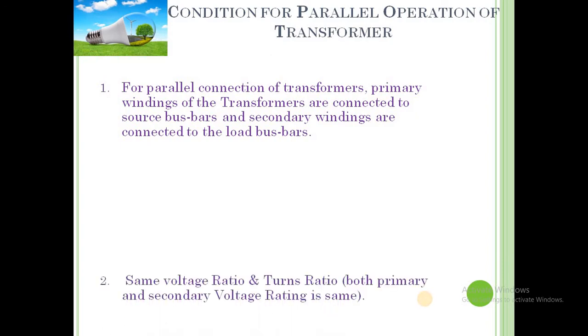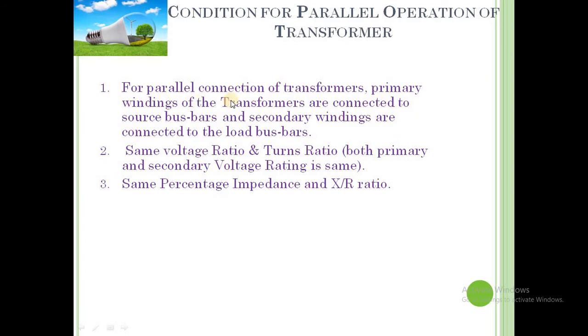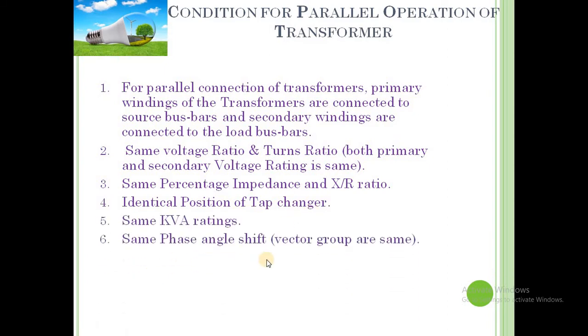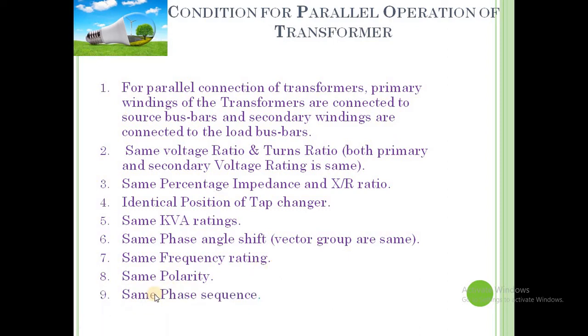Now for parallel operation, what are the conditions, we will see one by one. So for parallel connection of transformers, the primary winding of both transformers should be connected to the supply bus bar, and the secondary winding of the transformers should be connected to the load bus bar, that is the load which has to be supplied by the two or more transformers. Next, same voltage ratio and same turns ratio of the transformers, same percentage impedance and X by R ratio, identical position of tap changer, same kVA ratings, same phase angle shift, that is the vector group of the two transformers which are going to be connected in parallel should be the same, same frequency rating, same polarity of the transformers, and the same phase sequence should be there. So these are the conditions which we should first check before connecting two or more transformers in parallel.